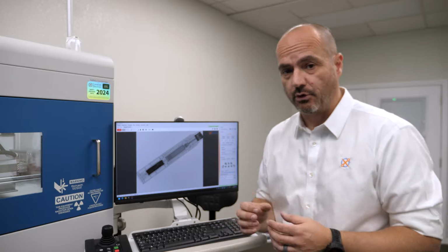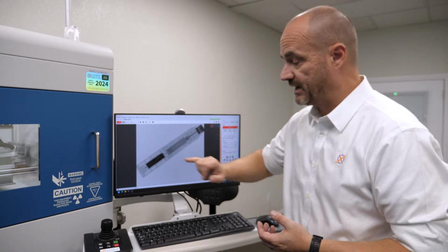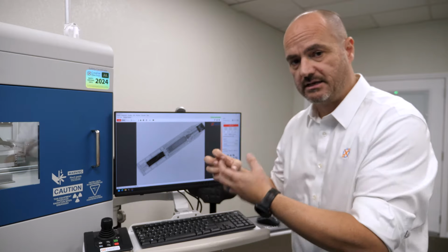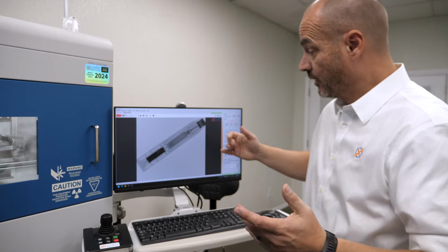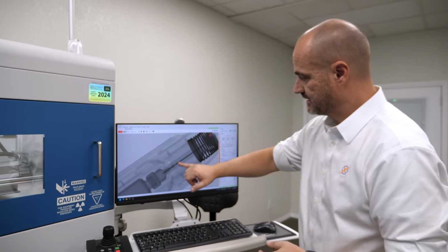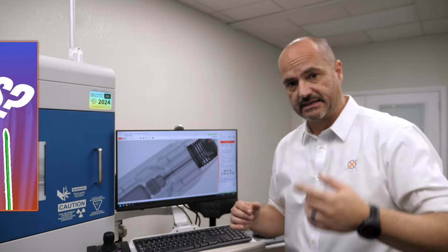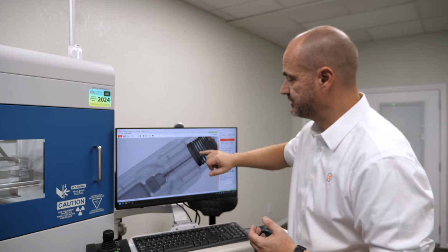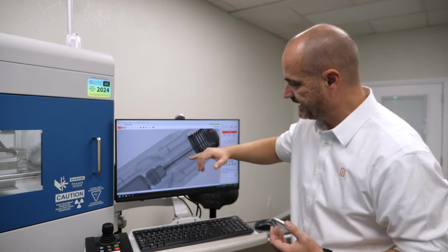And some of the things that you look for in the specific sample for quality, right? We have if the springs are correctly positioned, or if in any way they are defective and they've been compressed incorrectly and they don't sit in the plastic casing of this medical device. We can check if the needle is straight or if it's damaged in any way, right? We have a CT example that Anthony is going to put on the link here that shows how you can use computer vision to properly figure out if this needle is straight, or if there's a kink at the end, or if it's bent in the middle.